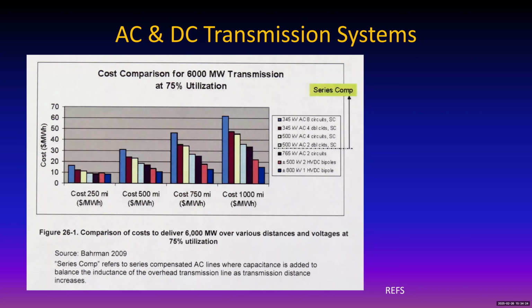But look at that light blue line at the beginning—that's for low voltage transmission, where it gets a whole lot more expensive for longer distances. Why is that? Because there's more losses—lower voltage means higher current, higher I-squared-R losses. So you want to transmit your electricity at the highest possible voltage.